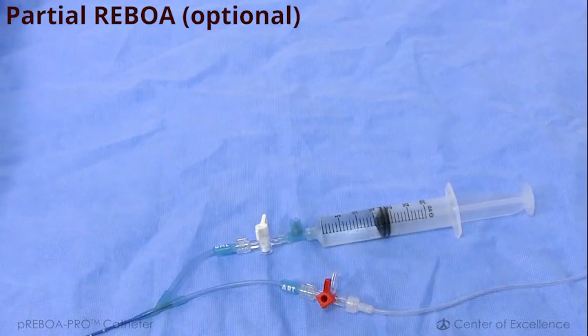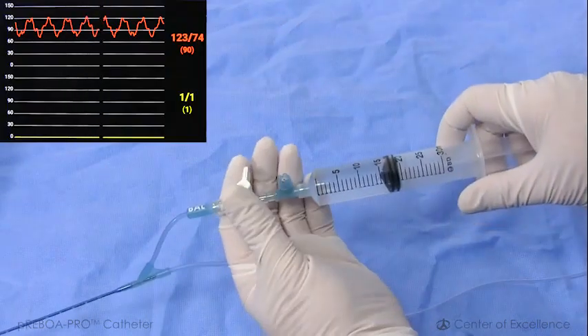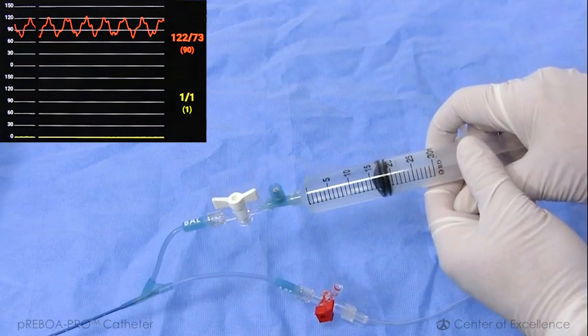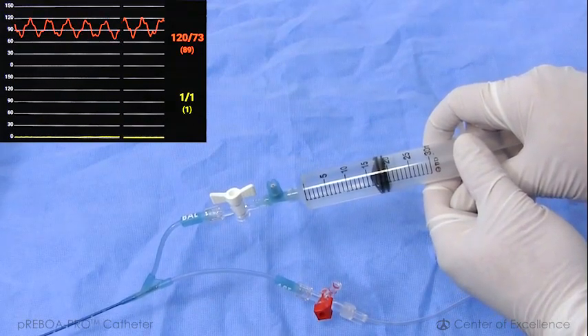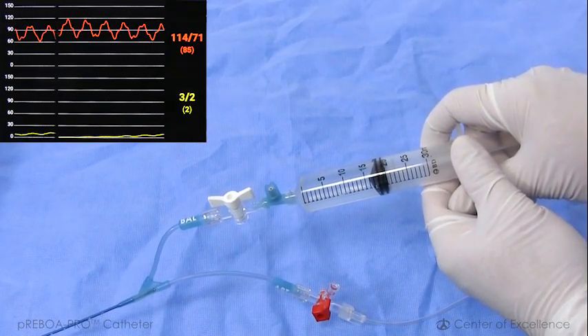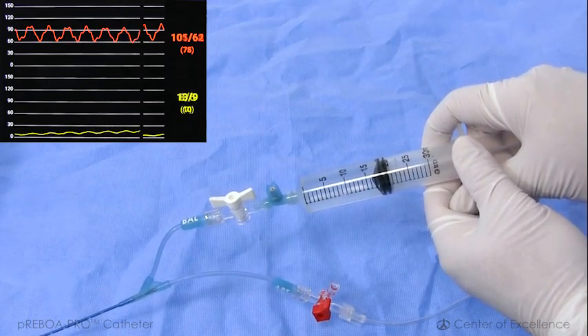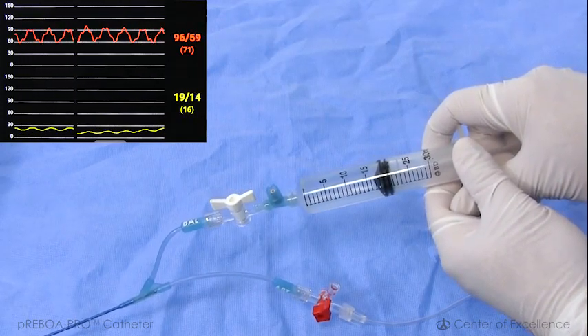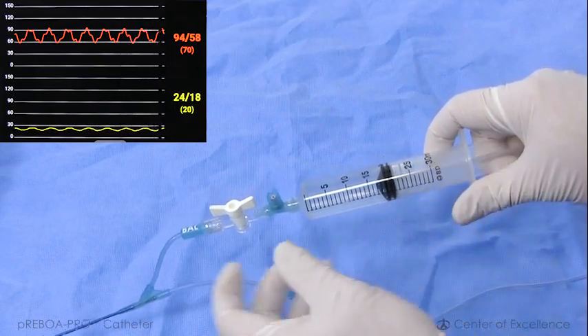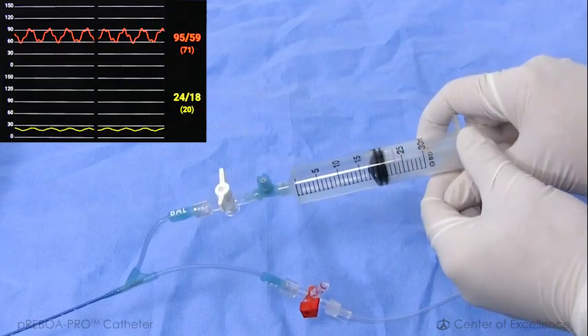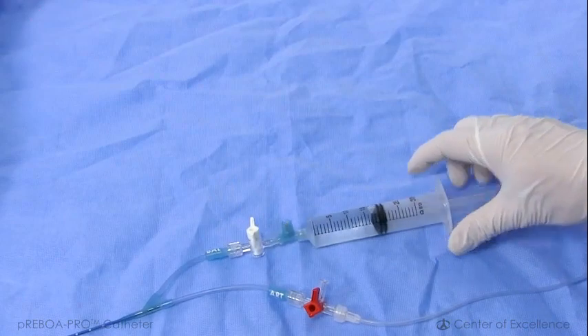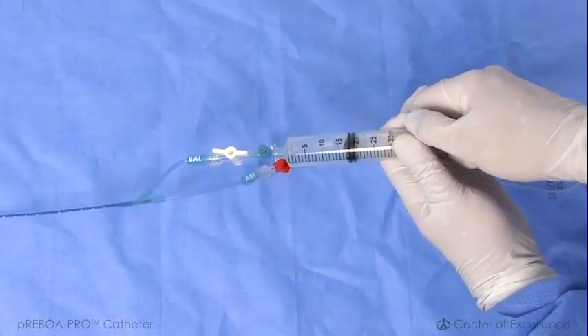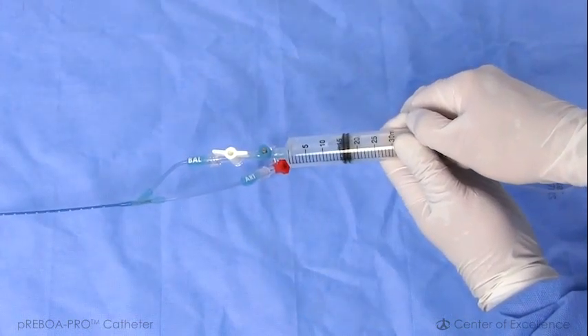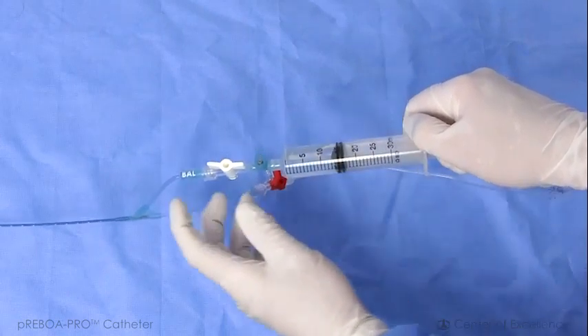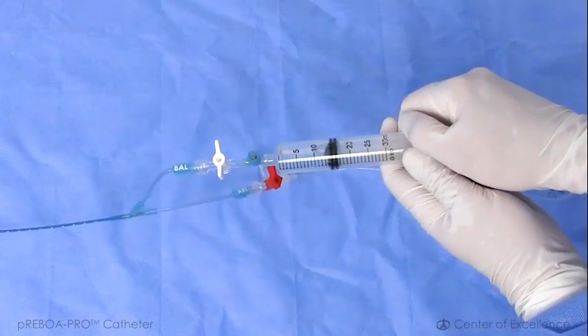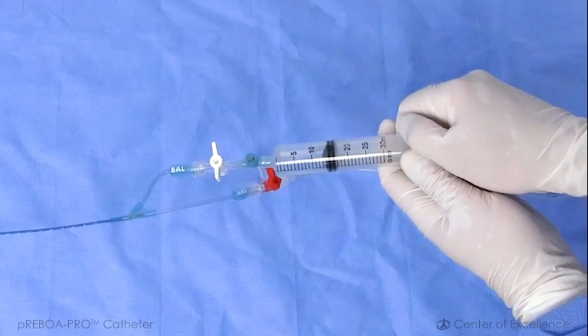To perform partial pREBOA, slowly deflate the balloon until the desired physiologic response has been achieved. When making minor adjustments, keep in mind that the numeric values on the vital signs monitor may be delayed from 3 to 10 seconds. So it is important to allow time for the monitor to normalize between adjustments. A 30cc syringe should always be used for initial inflation and final deflation. A stronger vacuum can be generated with a 30cc syringe, rather than a 10cc syringe.